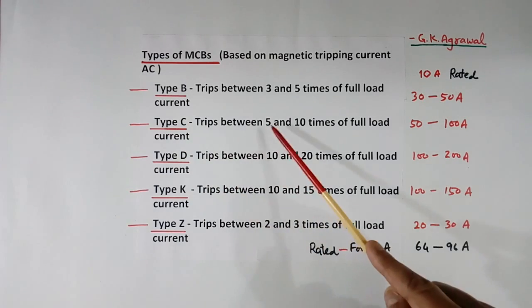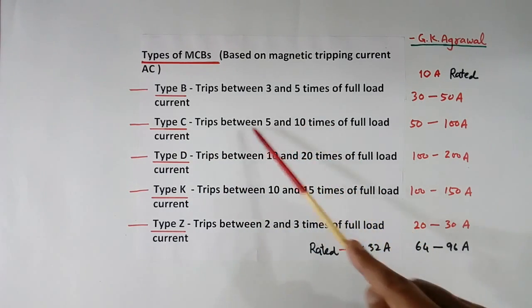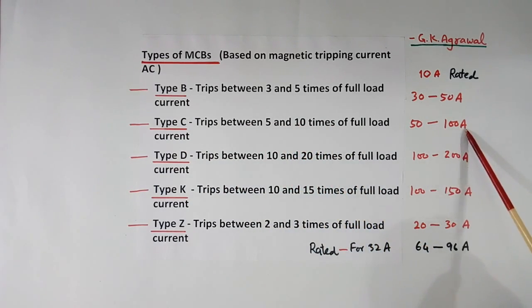Type C will trip between 5 and 10 times, means 50 to 100 A. Type D trips between 10 and 20 times. 10 means 100, 10 times. 20 times means 20 times. This is 100 A, this is 200 A. So type D will trip between 100 and 200 A for this MCB.